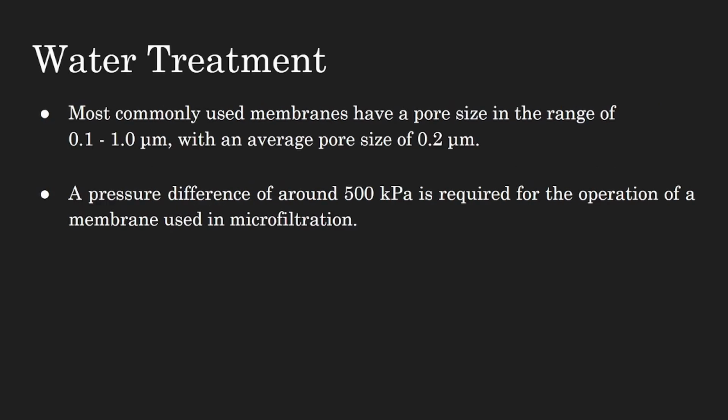Most commonly used membranes have a pore size in the range of 0.1 to 1 micron with an average pore size of 0.2 micron. A pressure difference of around 500 kilopascal is required for the operation of a membrane used in microfiltration in this case.